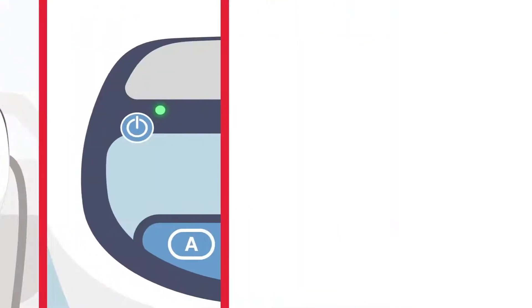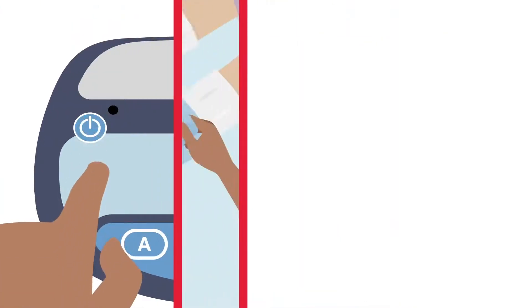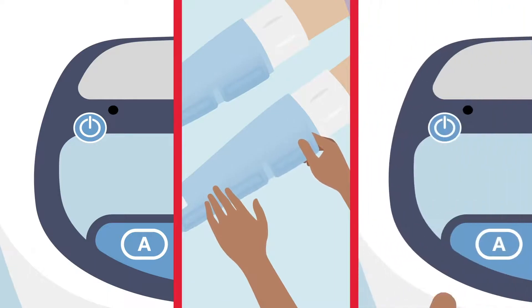To silence the alert, turn the controller off, reapply the sleeves to the patient, and turn the controller back on.